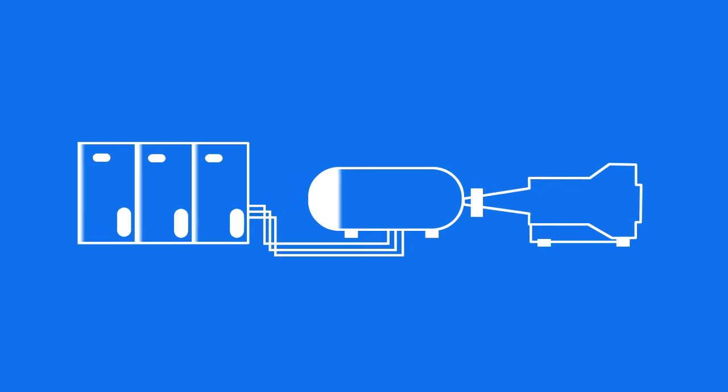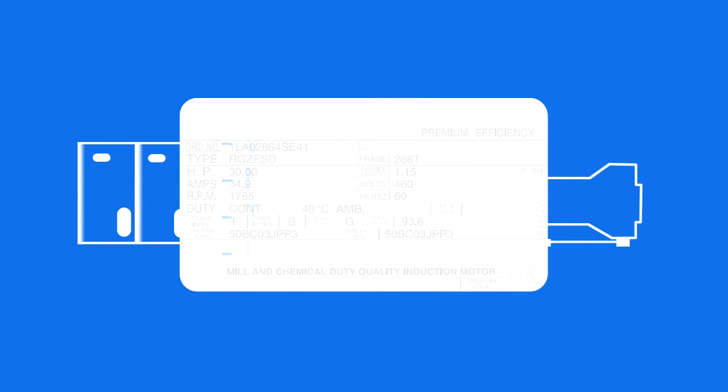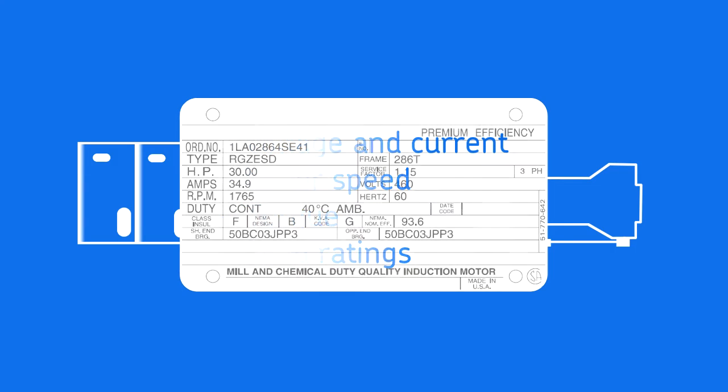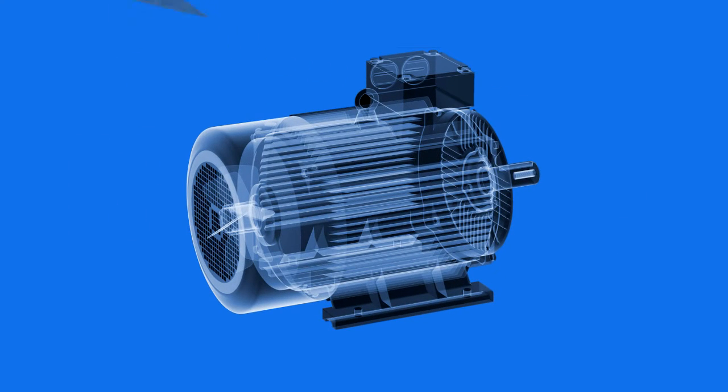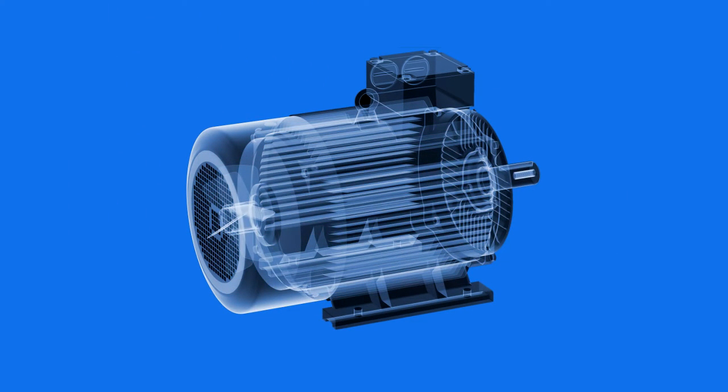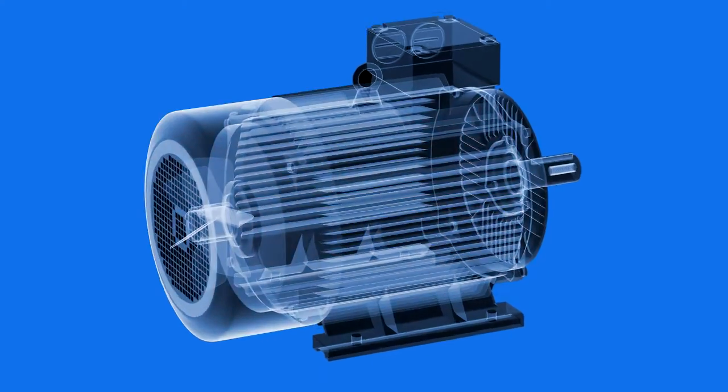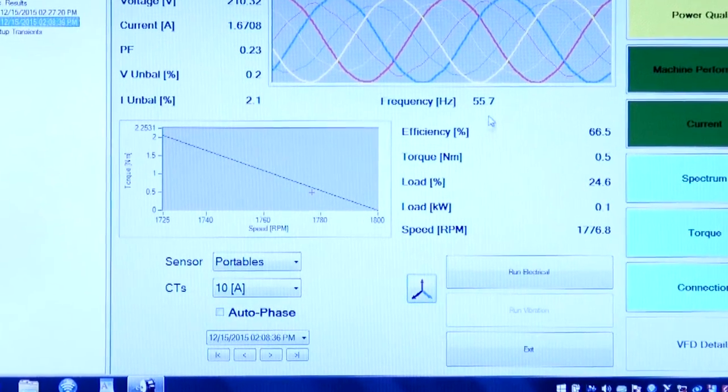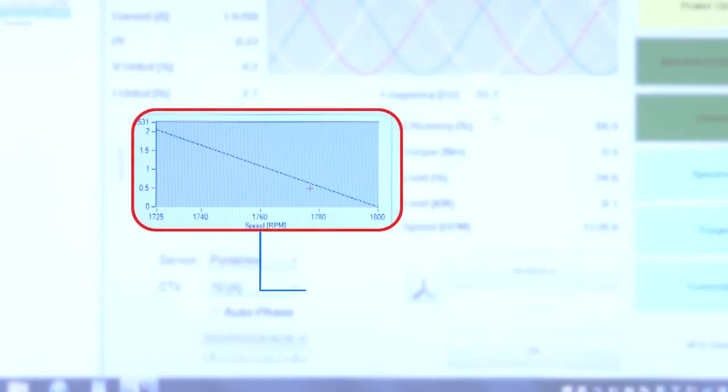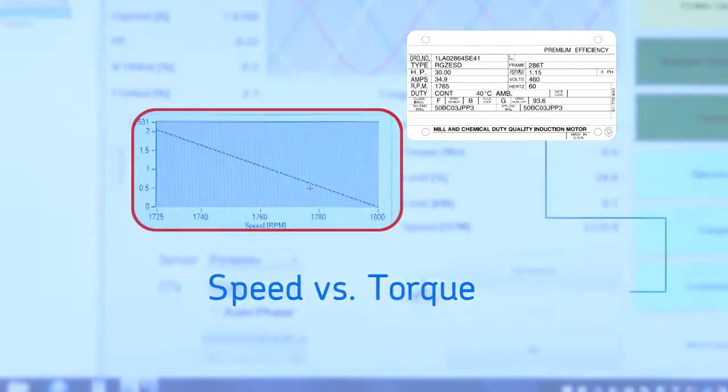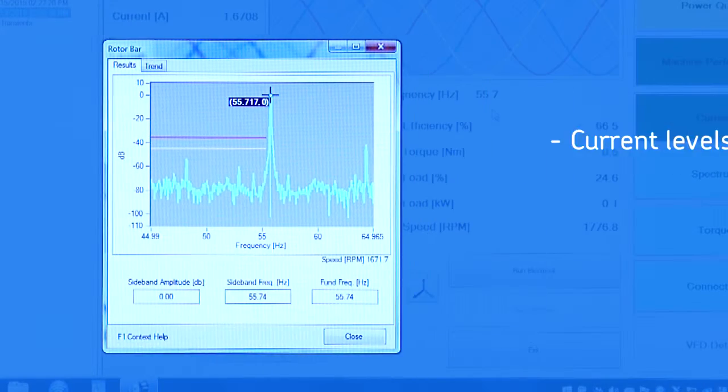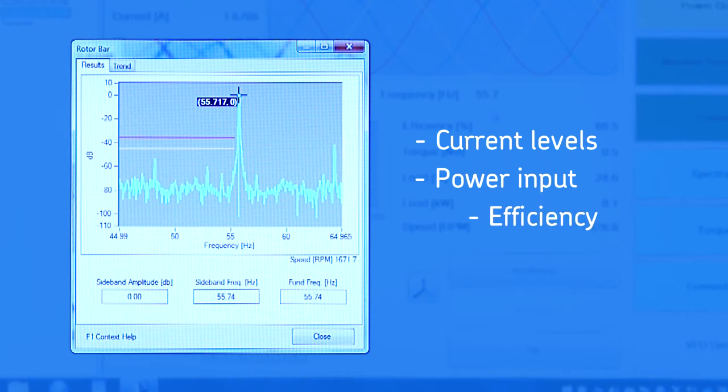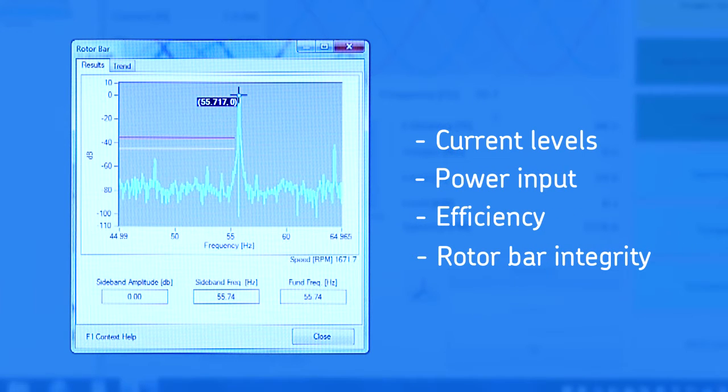Electric motors are designed for specific conditions found on the nameplate for the motor. This includes things such as voltage and current, but more importantly motor speed, torque, and load ratings. Running a motor in an overloaded condition can quickly reduce the motor lifetime. SKF Dynamic Motor Monitoring Solutions measure the motor output, speed and torque, and compares it with nameplate values. Current levels, power input, efficiency, and rotor bar integrity are also measured.